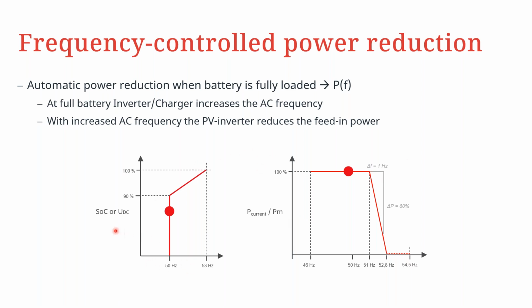So we have, to the left, the state of charge of the battery versus the operating frequency, as well as the maximum power production by the Fronius inverter versus the operating frequency. So as you can see, as the state of the battery approaches 90% or reaches 90%, the battery inverter in this case reacts by increasing the frequency, and it will start from 50 hertz all the way to 53 hertz. And this is up to when the battery then is fully charged at around 53 hertz.